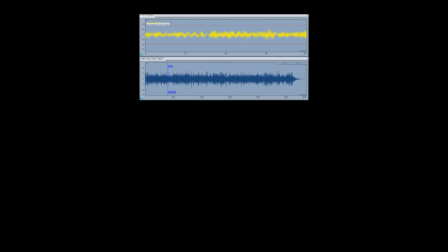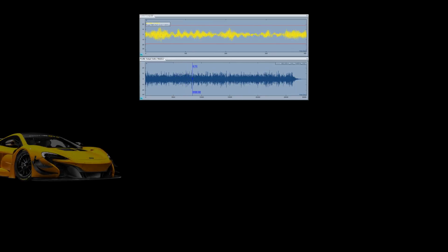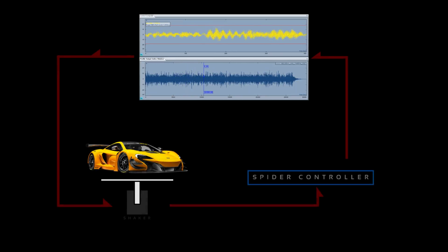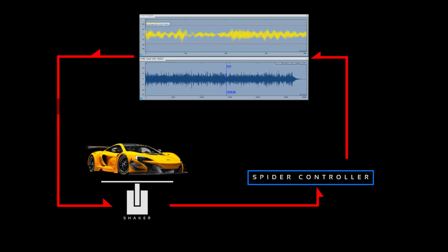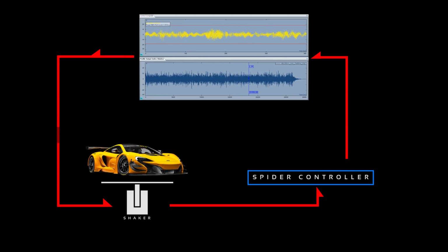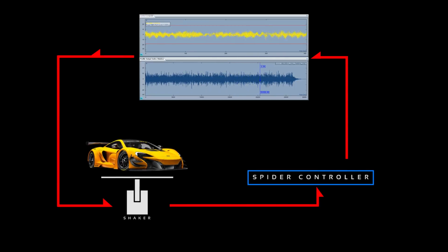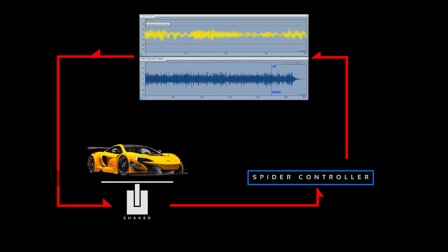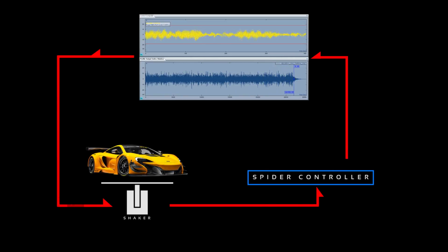In TWR tests, a predefined time domain waveform is replicated, and the structure under test is excited using this waveform. The response of the unit under test is measured, and the output signal is varied in closed loop to maintain the input control signal same as that of the predefined waveform. We've designed Waveform Editor and EDM application as a supplementary tool to create and modify waveforms.